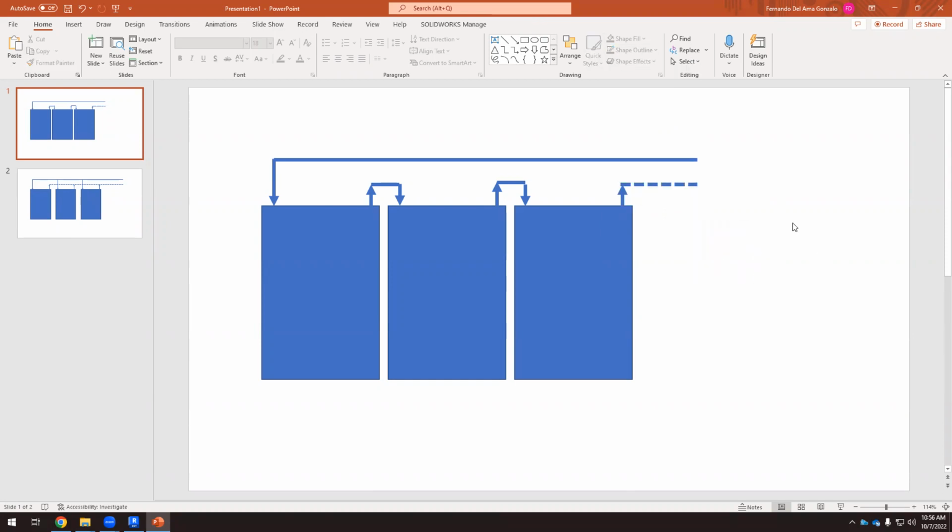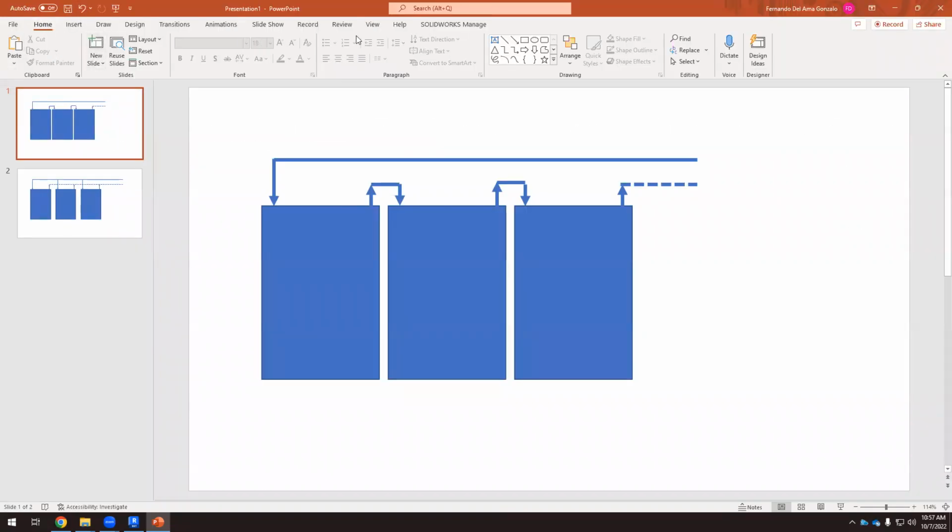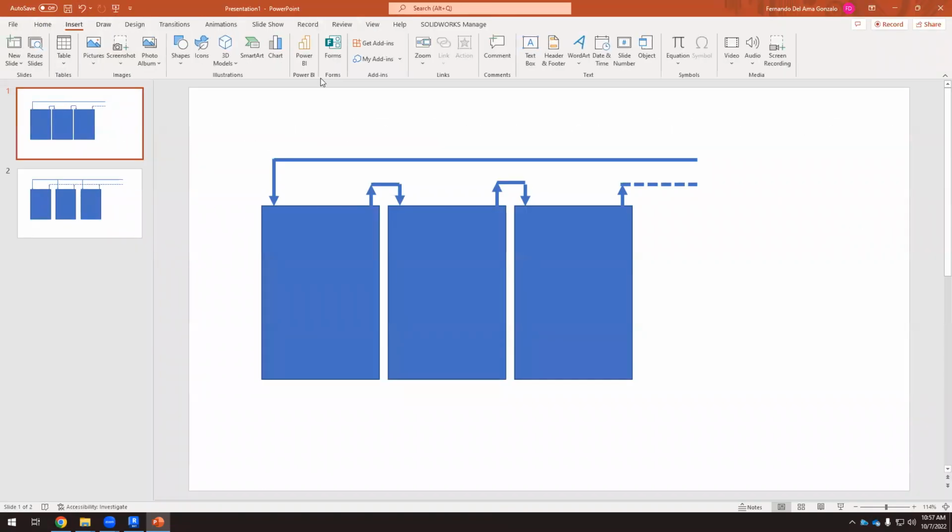Okay, so that actually matters. And if you're a plumber, you have to put a lot of thought into it because that affects how the system works. Imagine that this is the inlet. So this is the solar collector. So the water here, the inlet is cold, and we have to heat up this water. So imagine that each panel heats up the water like 10 Fahrenheit. Okay, so that depends on the specification of the panel, but let's try to understand how it works.